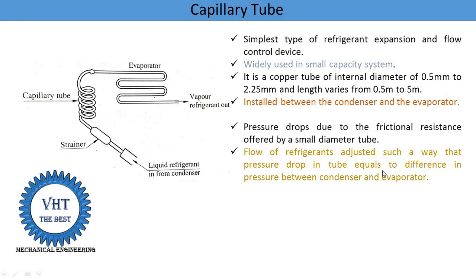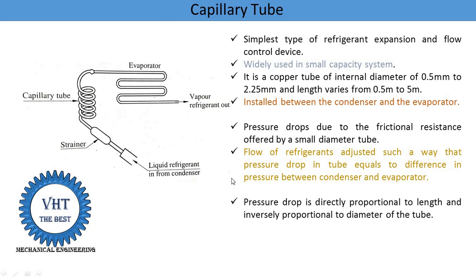The flow of refrigerant is such that the pressure drop inside the capillary tube equals the pressure difference between the condenser and evaporator. This pressure drop is directly proportional to the length — if we increase the length of the capillary tube, pressure drop increases. The pressure drop is inversely proportional to the diameter of the capillary tube — if we increase the diameter, pressure drop is reduced.